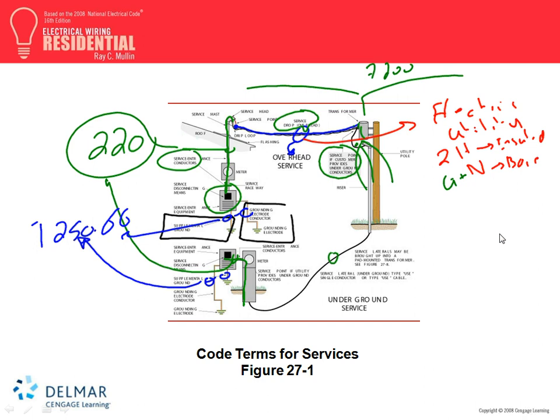If I'm to summarize, guys, remember the service drop or service lateral. These are the utility cables, with no jurisdiction over them. Service drop, service lateral, if the point of common coupling is here, then remember the service entrance conductors that we size coming from here, or sometimes it might come all the way from here. Let's just say the service point is right here at the meter, so we're bringing our service to the equipment. That's service conductors.